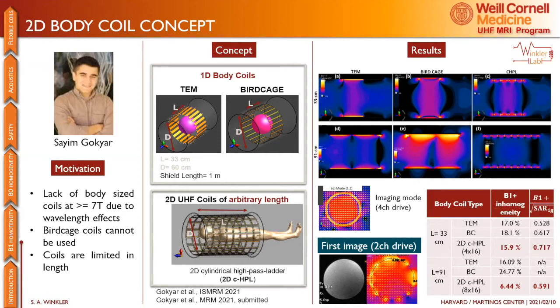So the problem here is that the reason such a thing does not exist is because at 7 Tesla or higher, the wavelength effects become so significant. As we said, in tissue, the wavelength is 13 centimeters. It's a bit longer out of tissue. So you can't really use birdcage coils anymore at that size. You still use it for head dimensions, but not for body dimensions. And another aspect here is that the coils are limited in length because of these wavelength effects.